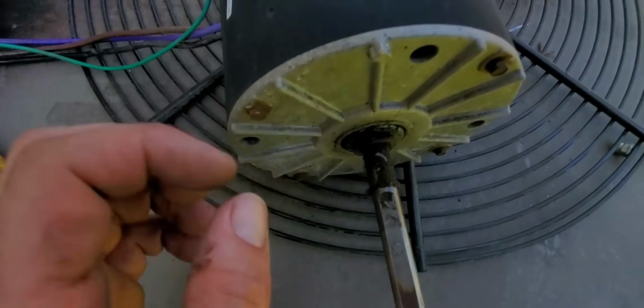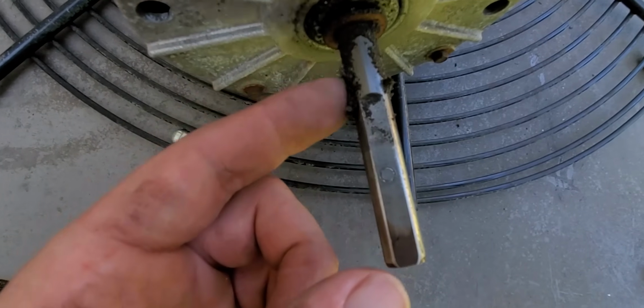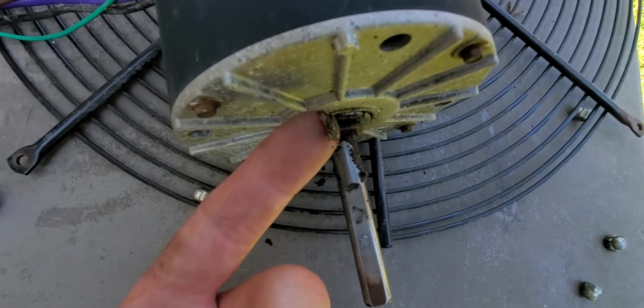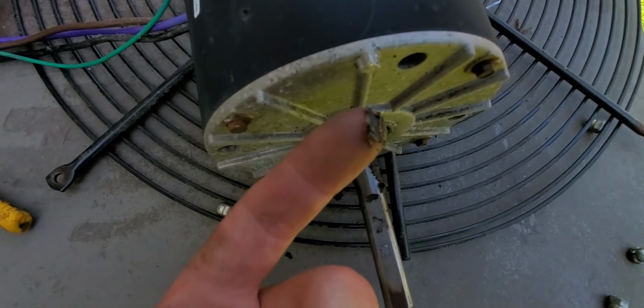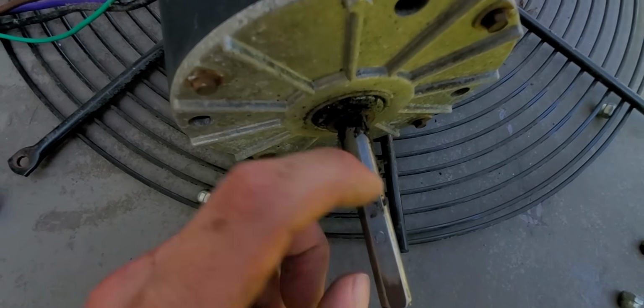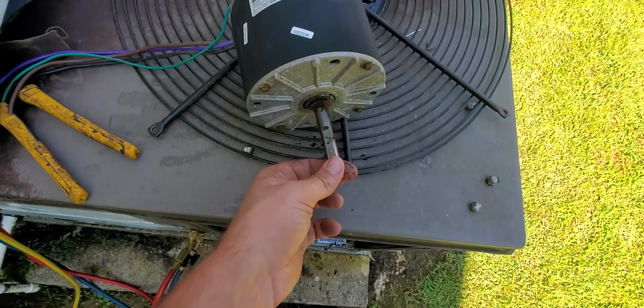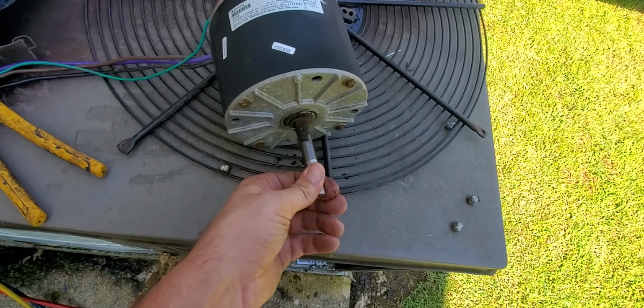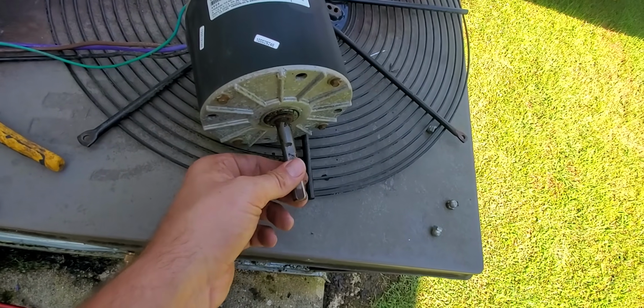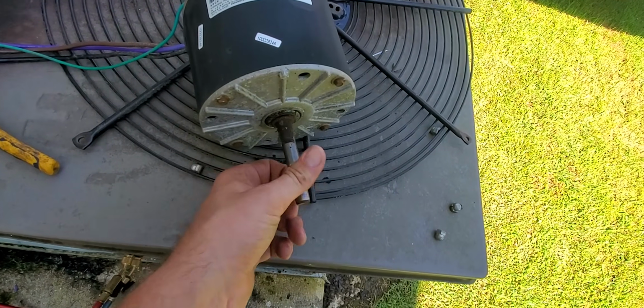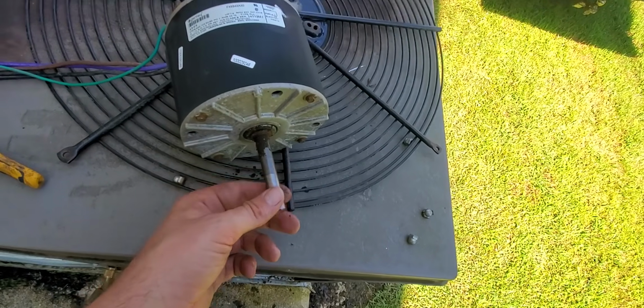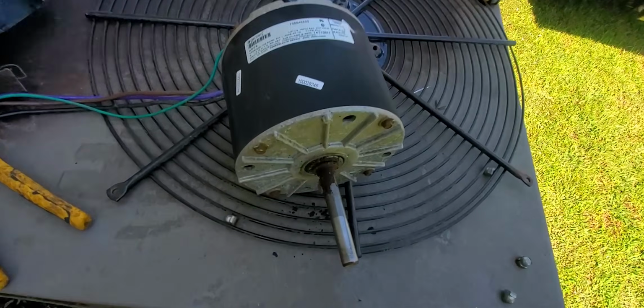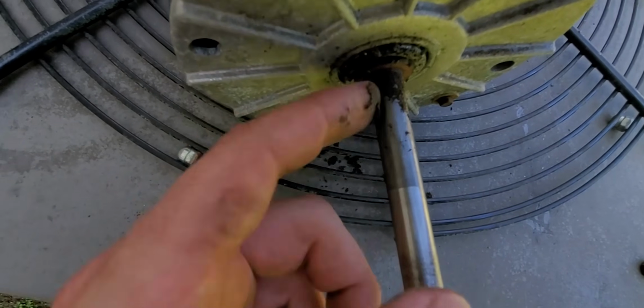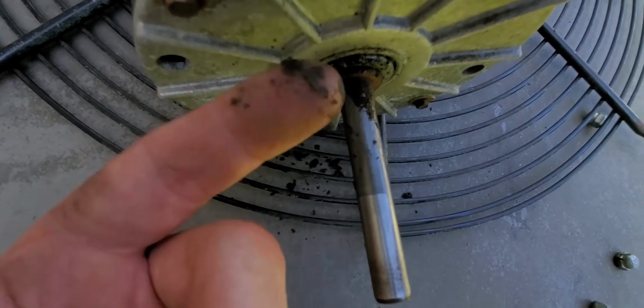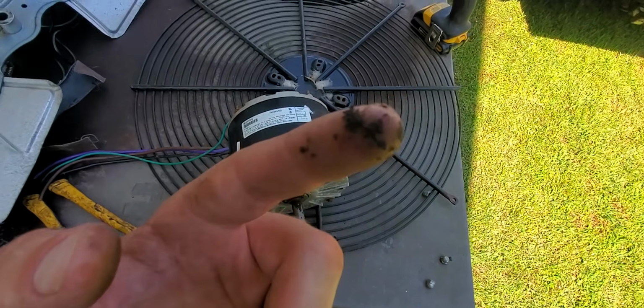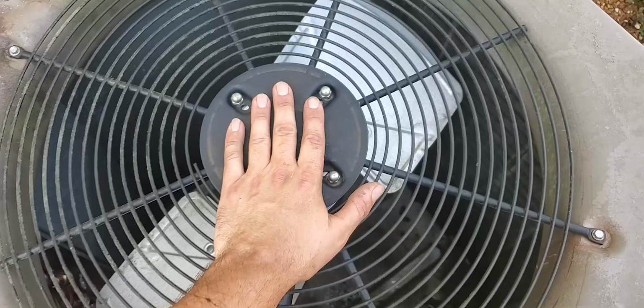If you see this right here coming out of the motor, then it's likely that the bearings are going to be going bad before too long. It's going to start creating some rough movement here when you try to move the shaft. So side to side, if it's got slack, bearings are bad. If you move it and it's rough when you turn it, you can't really turn it, that means it's bad. Also, this oily dust here that comes out of the motor is an indication your motor's going bad. New motor's on.